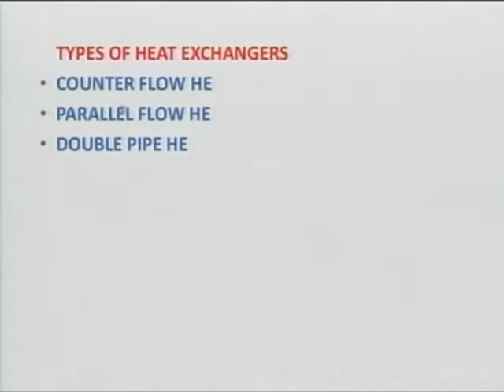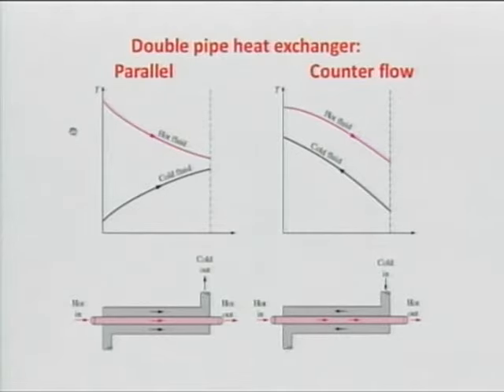There are various types of heat exchangers: counter flow, parallel flow, double pipe. I am going to take tube-in-tube because I am sure all of us have built tube-in-tube heat exchangers in our labs. What is the typical wattage for which a tube-in-tube heat exchanger is used, for single-phase only? Typically I will not go above 6 to 10 kilowatts.